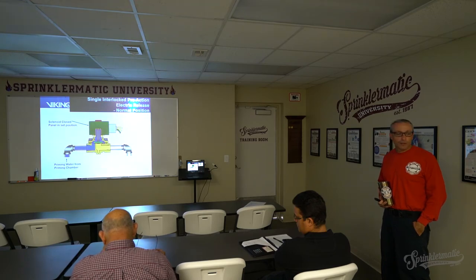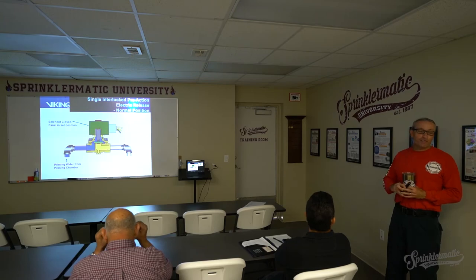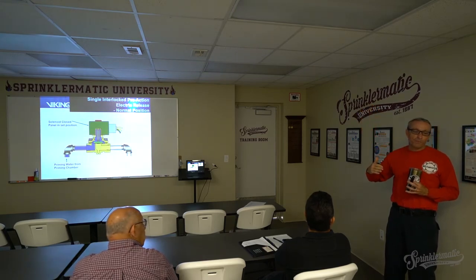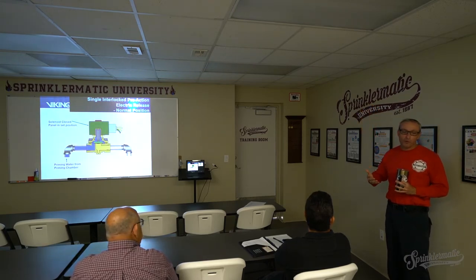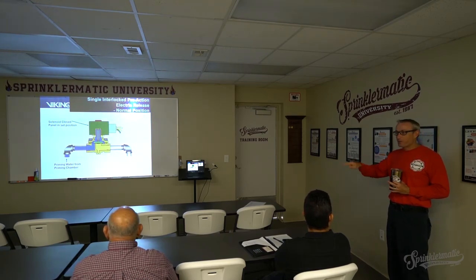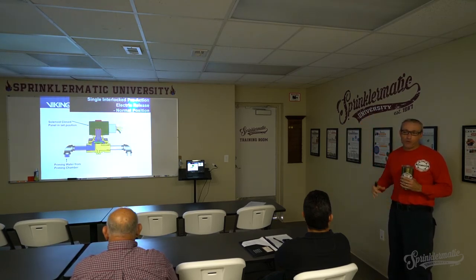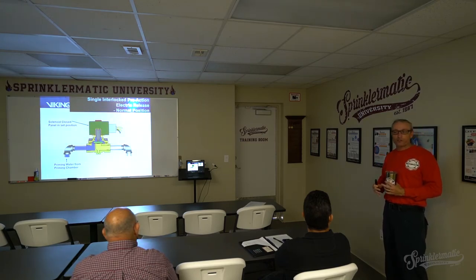That was a big fine, though. Yeah, it was. Well, how long has it been there? What I want to know, because having the seventh floor valve on the first floor, that's not really a big problem, because we can overcome that. But I want to know where the one that's supposed to be on the first floor is. If the one that's on the first floor is on the seventh floor, now we have an issue, because then we have more pressure restriction going on.